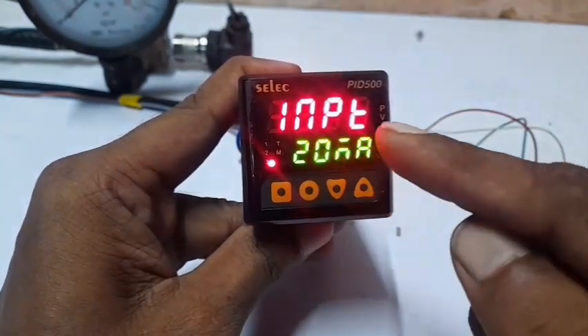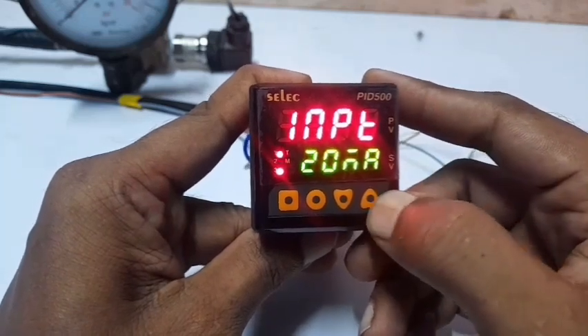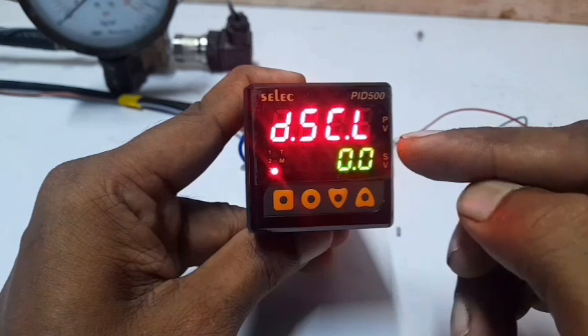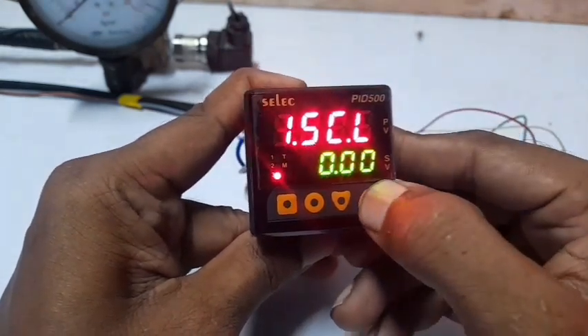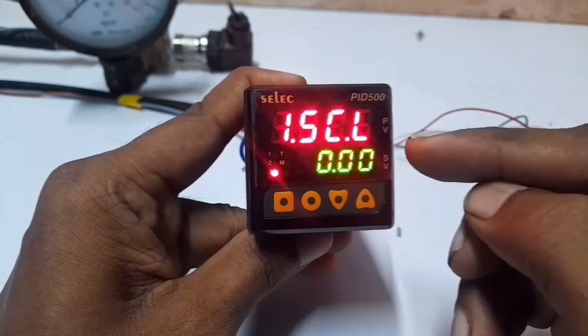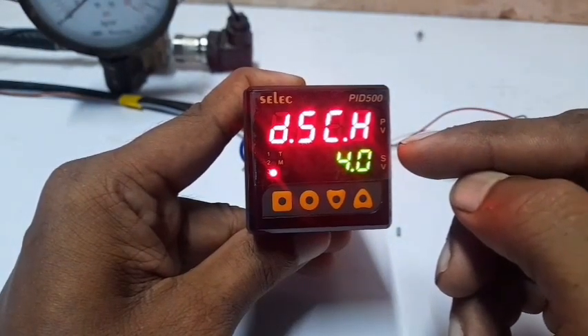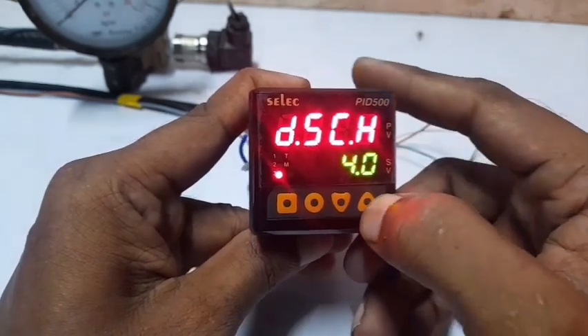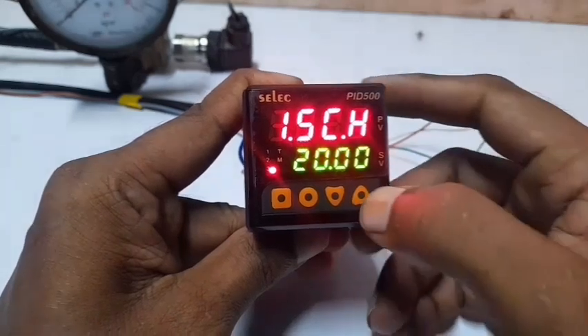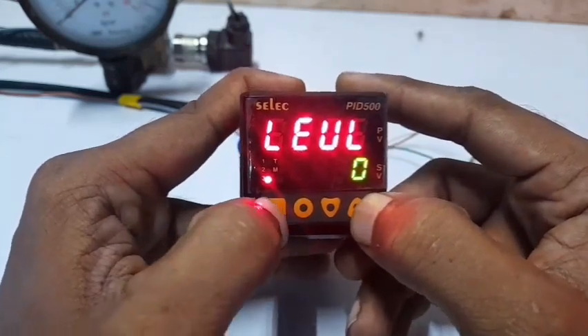This setting is for 4 to 20 milliamps — the transmitter can measure pressure. Next, set the resolution to 0.01 for the display. Set the display scale low level to 0 (the pressure display shows 0.0). The input scale low value is 4 milliamps (for 4 to 20 milliamps). The transmitter maximum level is 4 bar, so set the high input scale to 4 bar at 20 milliamps. Resolution is 999 for the high scale; low level 0 is done.